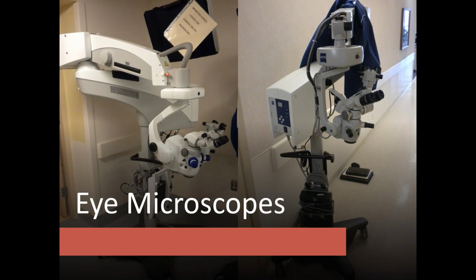So that the surgeon can record or take stills of the cases. These are the ophthalmology scopes. Typically you'll see Zeiss and Leica and then Alcon as well. But with these, the two that you see here, one is electrically controlled and one is manually controlled. As Clayton talked about a little bit earlier, the surgeon can use the electromagnetic brakes to position the scope, let go, and it stays there. However, if the head is already draped prior to the case and somebody has to get in and make any type of movements, there is this brake release bar up here on the top of the flex arm.